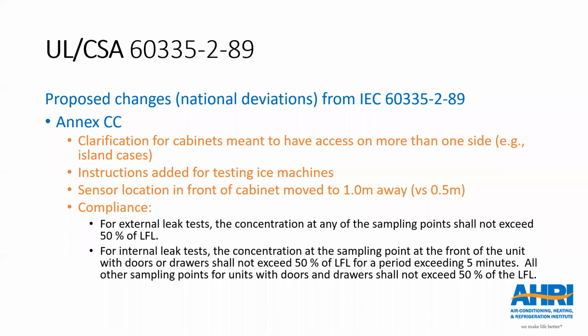Additionally, instructions have been added for testing ice machines. The refrigerant concentration sensor in front of the cabinet has been moved from half a meter to 1 meter away. This was done to account for the aisle space that must be in front of the appliance and the fact that it's very unlikely for a potential ignition source to be present in that aisle or walkway at any given time. Finally, the compliance criteria has changed slightly.